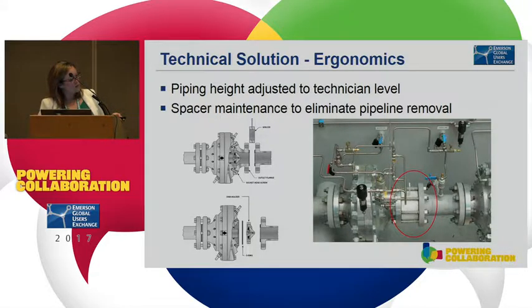It's a flange, wafer design spool piece. We pop off the top set of bolts, leave the bottom ones in place, and pull this whole spacer out. Undo the bolts around the edge here, slide this piece along the lower bolts we left on, and we have access to our seat and disc, which is the thing that will fail first if debris comes through the line. That's where you lose your lockup, and that's the most common type of maintenance done on this product.